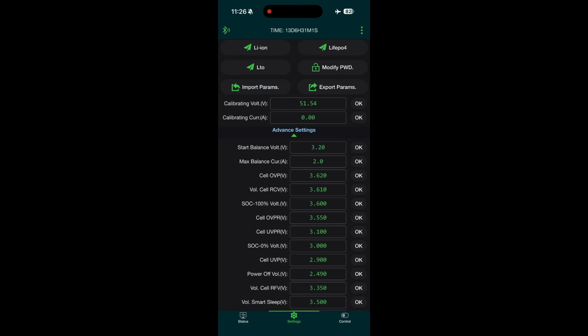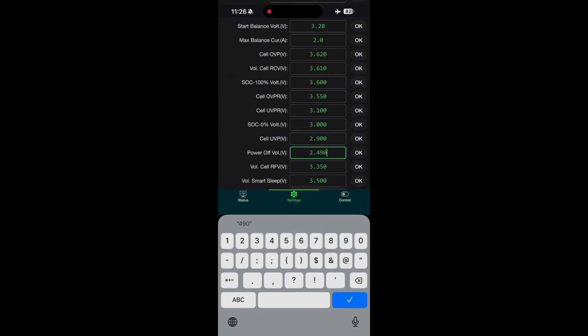Power off — this is where you want the BMS to actually turn off once it reaches this voltage. Even if discharge stops at 2.9, the BMS is still using a little power, and if you've walked away for days or weeks, it'll continue to discharge. So this setting is the voltage at which, once any cell reaches it, the BMS will turn off. I'll put it at 2.5.